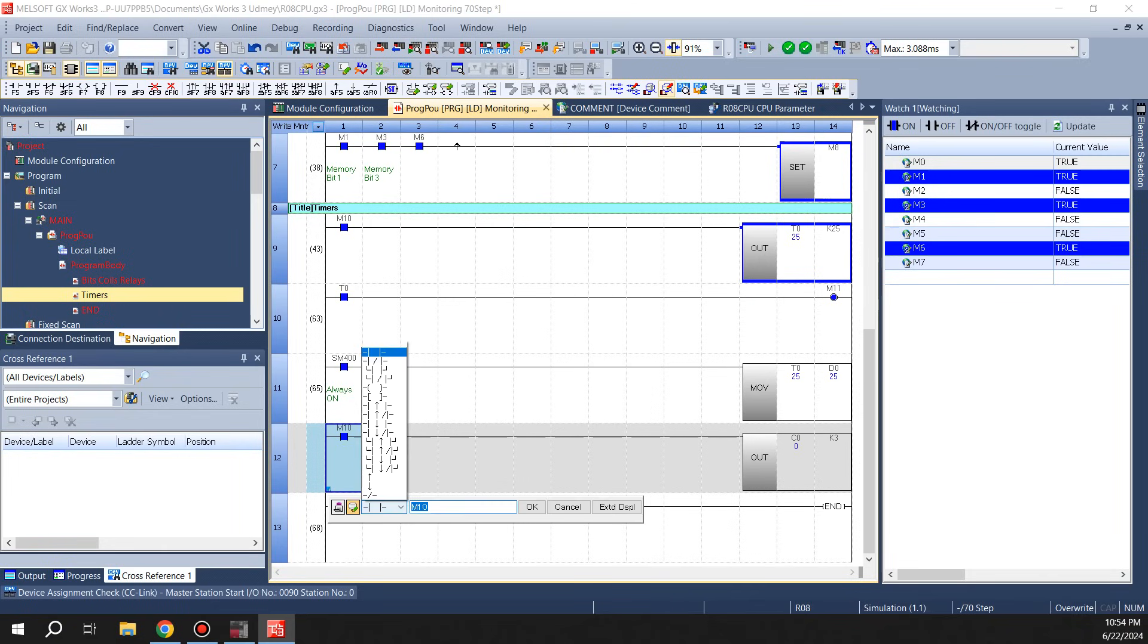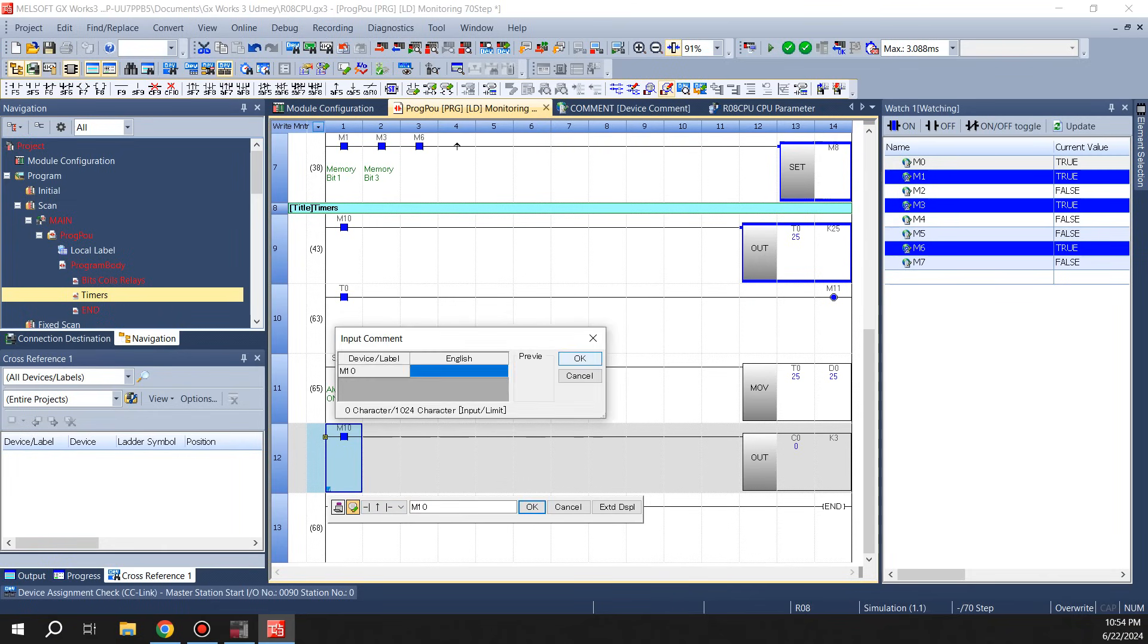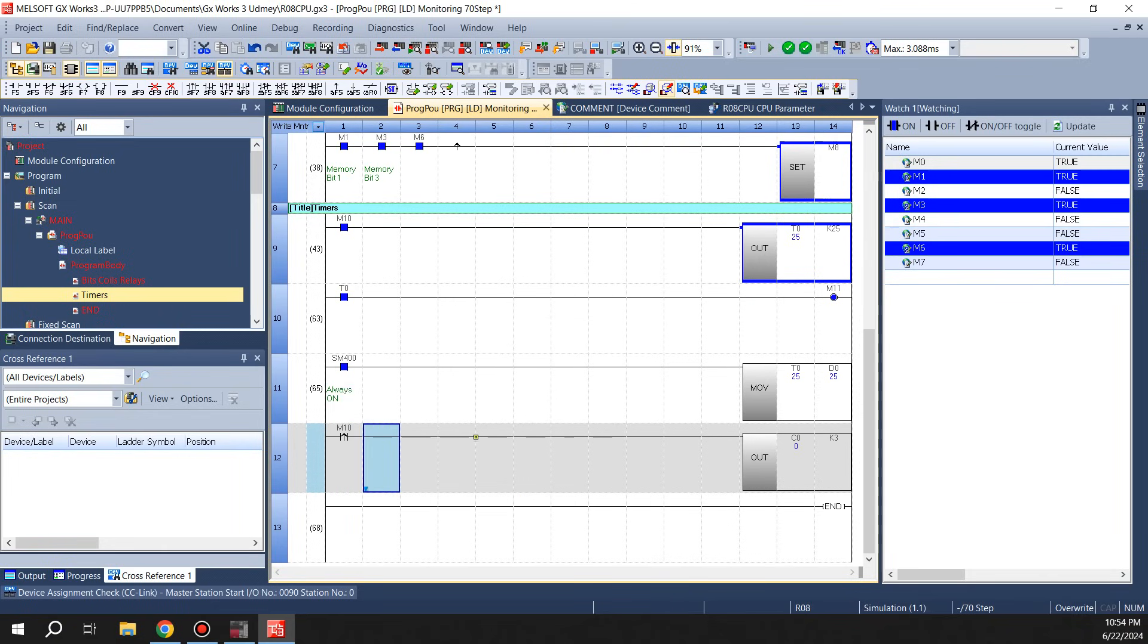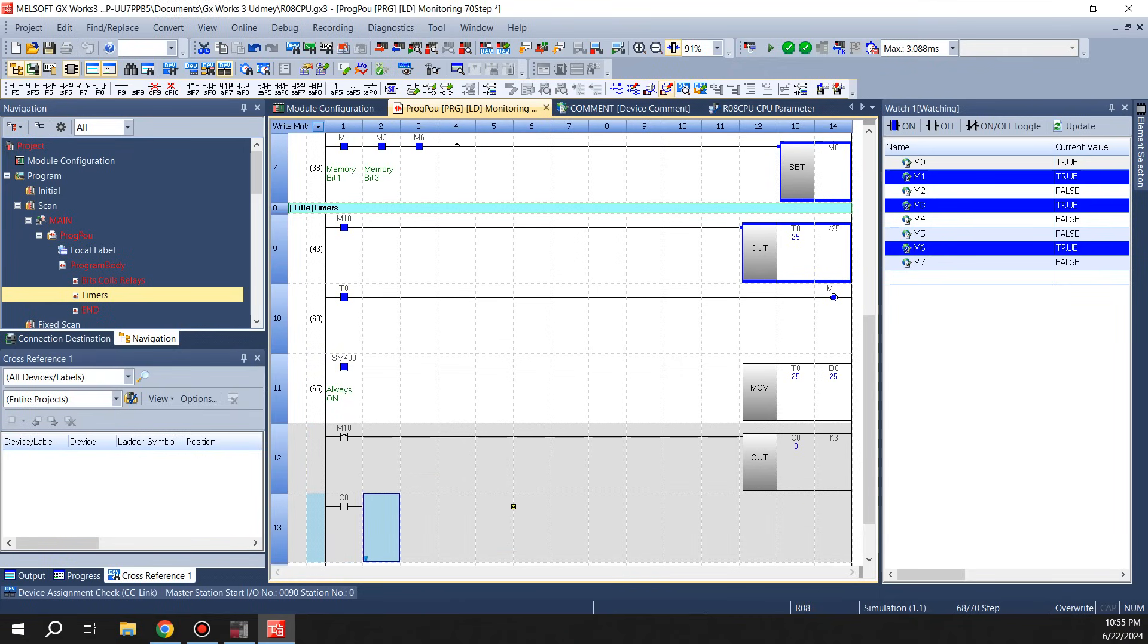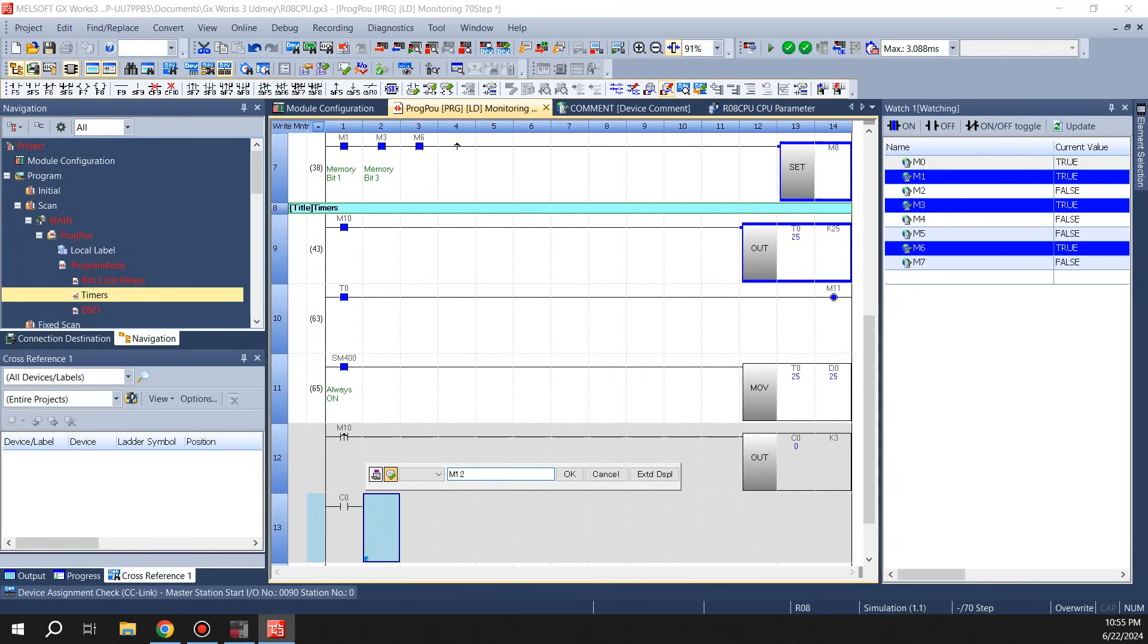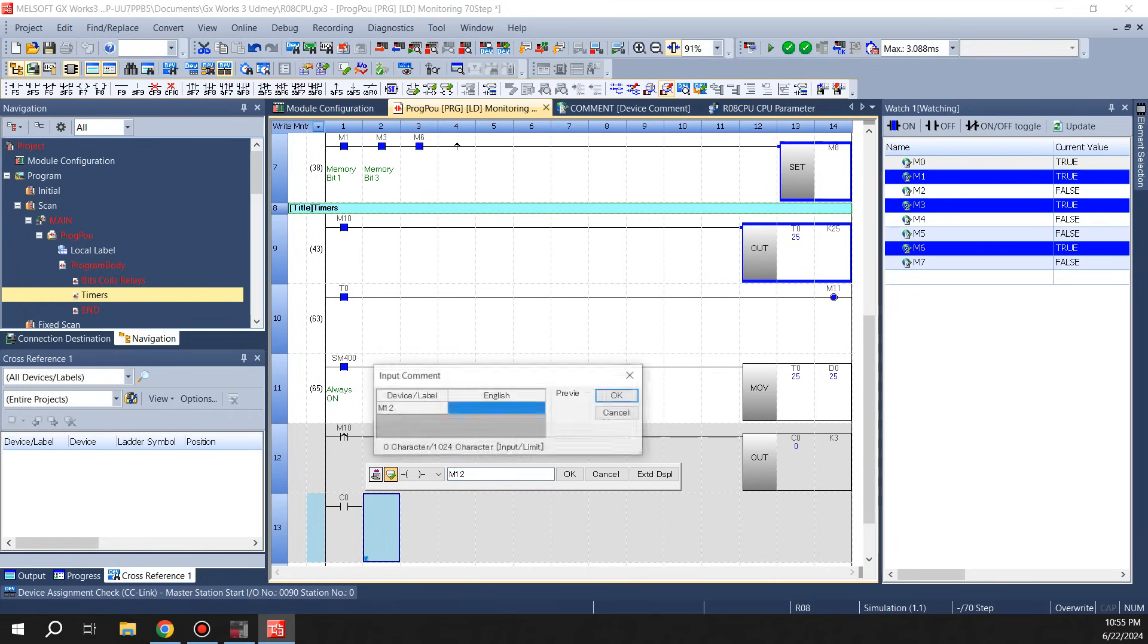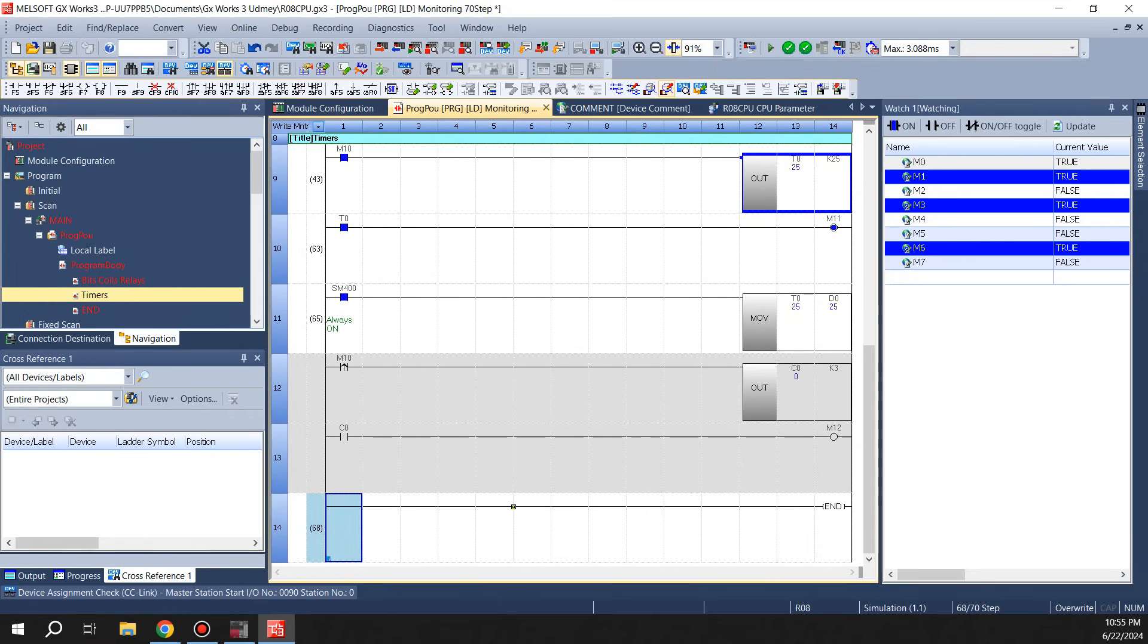What we'll do is we'll do a rising edge pulse of this thing so we can toggle it a couple of times and get a counter to count up. Because this is not a one shot, if you leave the rung in front of it on, it's gonna keep on counting every scan. So you have to have a one shot in front of it. See here, what we will do is we'll do a C0 and M12.